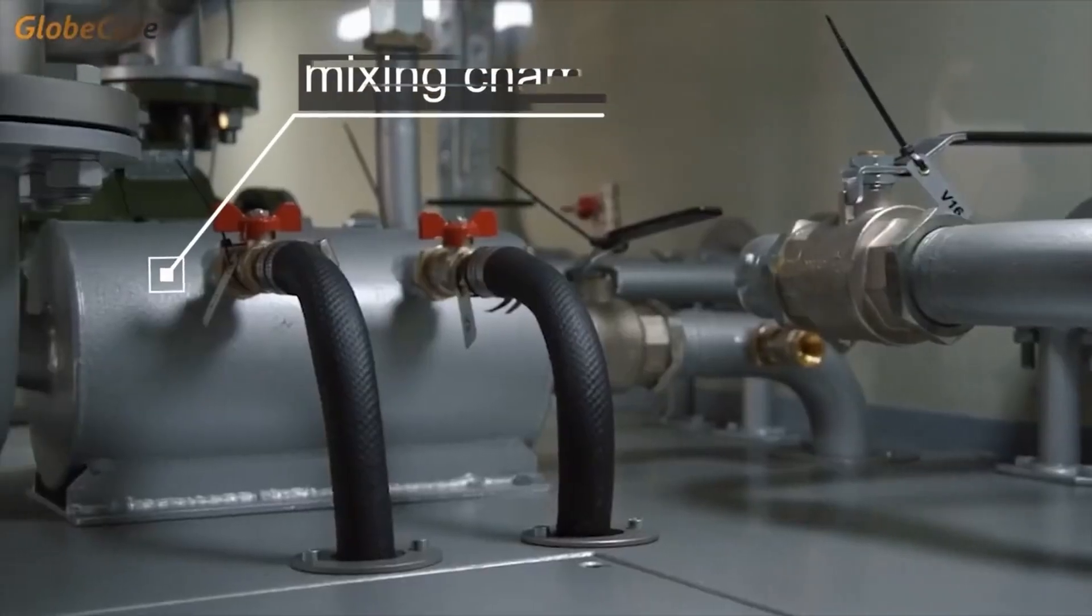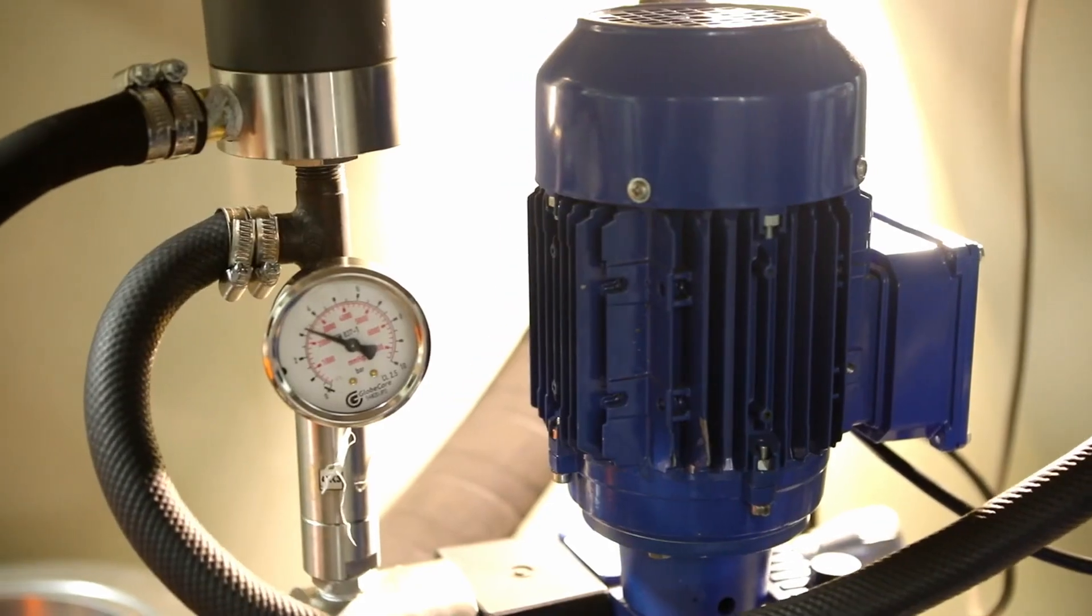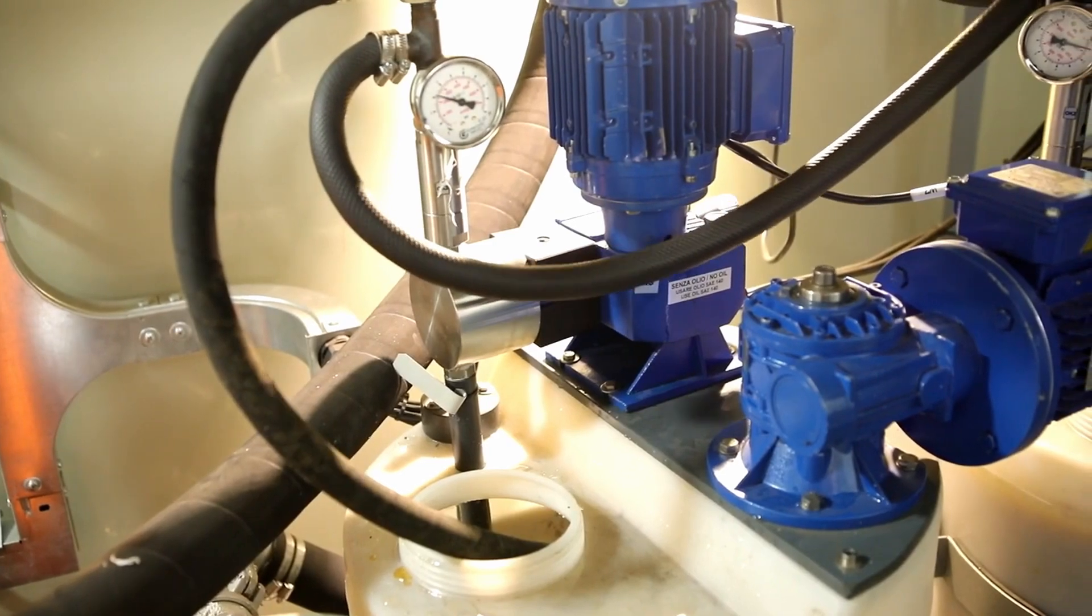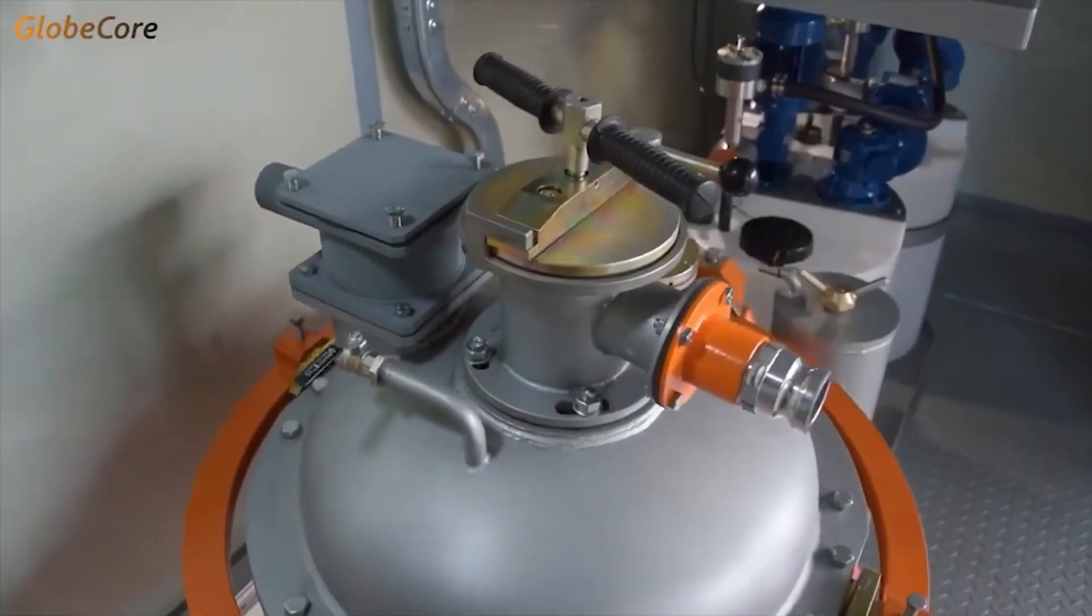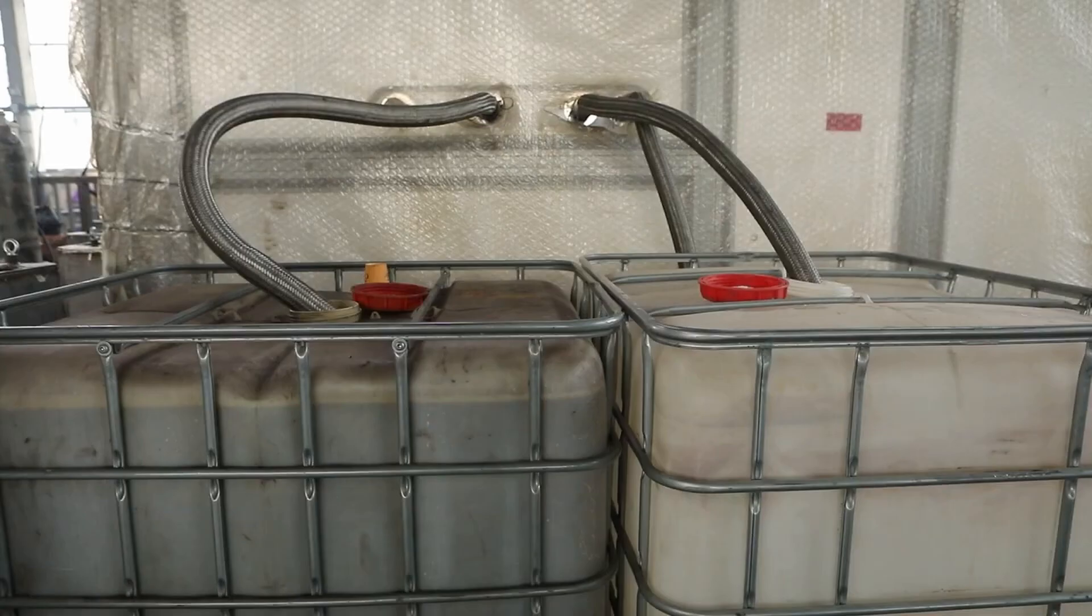The water enters the mixing chamber where a chemical agent solution, that is iron sulfate, is supplied by a dosing pump. After pre-mixing, the water and the chemical agent enter the operating chamber of the vortex layer device where hexavalent chromium is converted to trivalent chromium, after which it enters the storage tank.